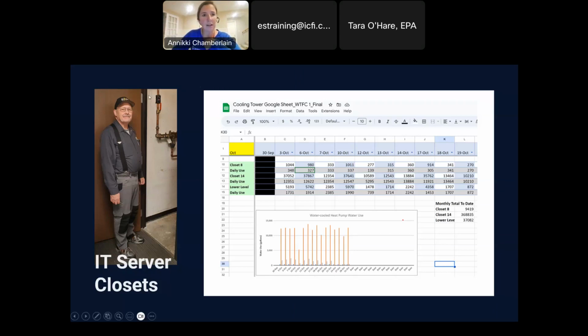You can see it right here. Every day, as part of his normal routine, he would walk the facility. I just made a Google Sheet that he could enter the information into on his phone. He would put in the meter read, and it would automatically do the calculations. So now we're getting the daily total water use for these condensers. What we can see here is the green, the orange is really high, this closet 14, and then there's a blue and a gray. I was like, man, that one closet uses so much more. Wow, it just must be quite a heat load.